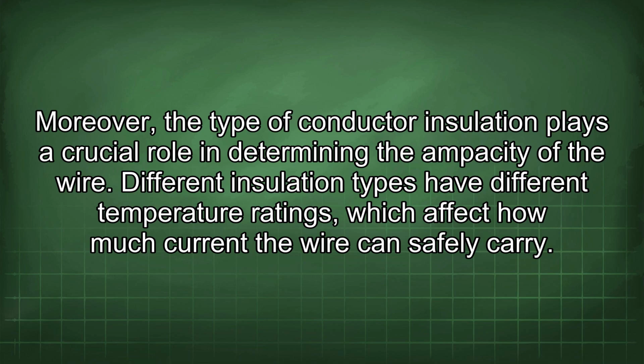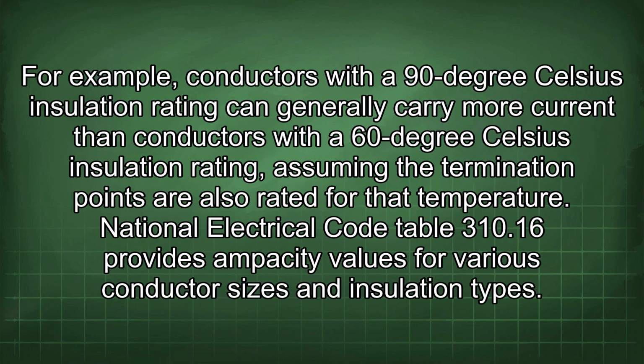Moreover, the type of conductor insulation plays a crucial role in determining the ampacity of the wire. Different insulation types have different temperature ratings, which affect how much current the wire can safely carry. For example, conductors with a 90 degrees Celsius insulation rating can generally carry more current than conductors with a 60 degrees Celsius insulation rating, assuming the termination points are also rated for that temperature.